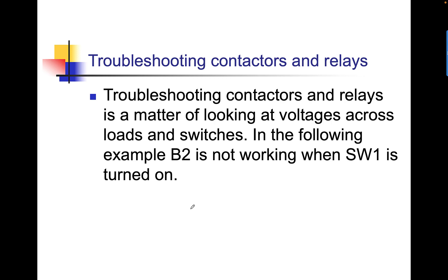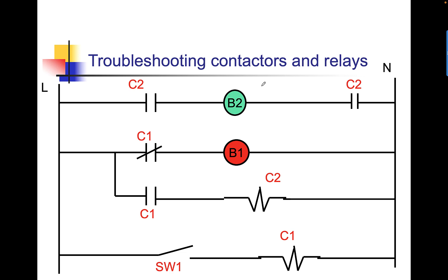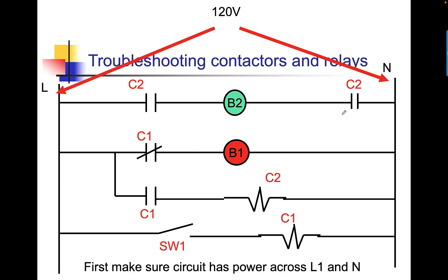Troubleshooting contactors and relays is a matter of looking at voltage across load and switches. In the following example, B2 is not working when SW1 is turned on. B2 is here. It's not working when we turn SW1 on. So, what is supposed to happen? If I close SW1, we energize C1. We close that one, the normally open. We open the normally closed. We energize the coil of C2, which should close C2 normally open contacts. That's what should happen. Now, we have to find out what's happening because you can't see these open and closed contacts. We first want to make sure we actually have power. We have power. We read 120.